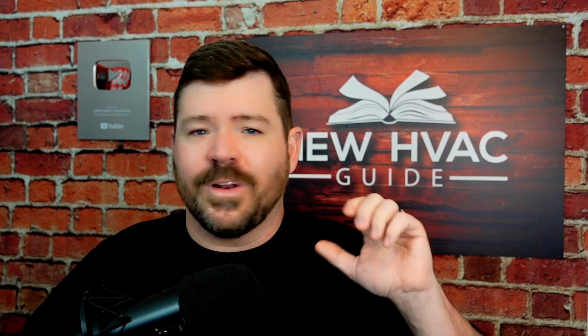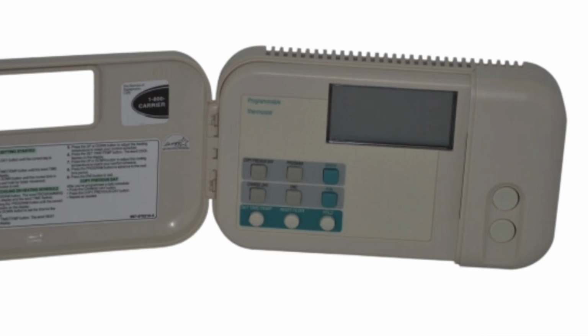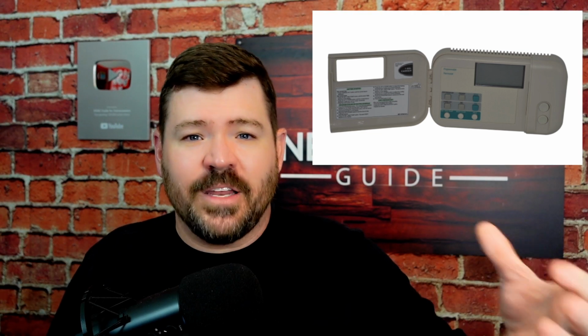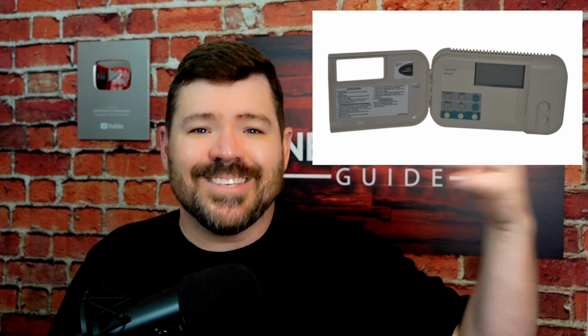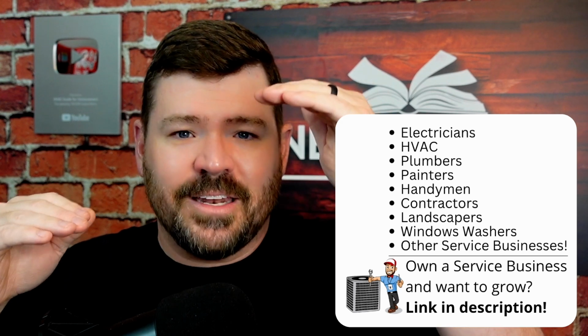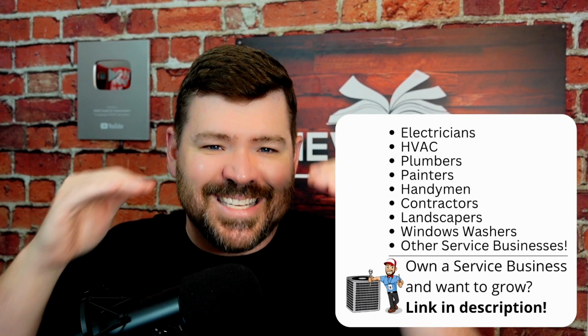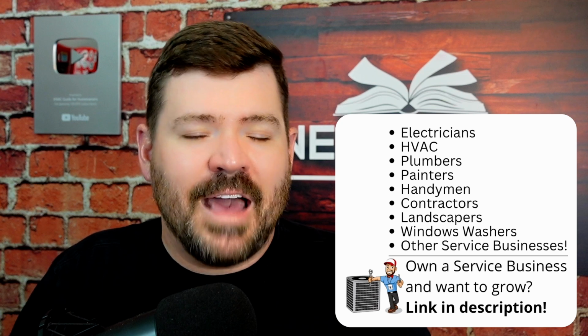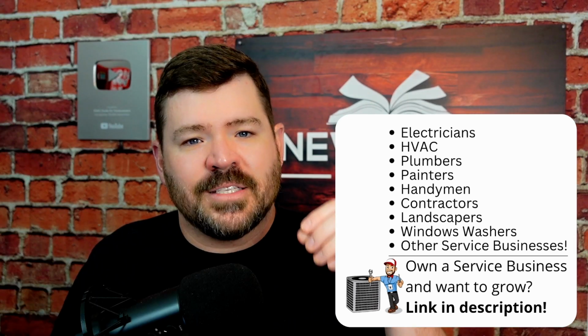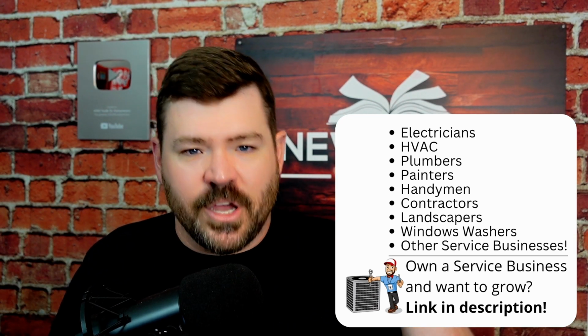I remember there were some old Carrier systems that used to have these controllers called Thermidistats, and they controlled humidity better than most cooling systems, and that's simply what it was doing. It was affecting the airflow, the speed of the motor, to increase latent capacity. The problem when you do that is you decrease sensible capacity in some cases. I mean, there are exceptions to every rule, but generally, if we're increasing latent capacity, we might be losing a little bit of sensible capacity, meaning you're not going to have as much oomph.